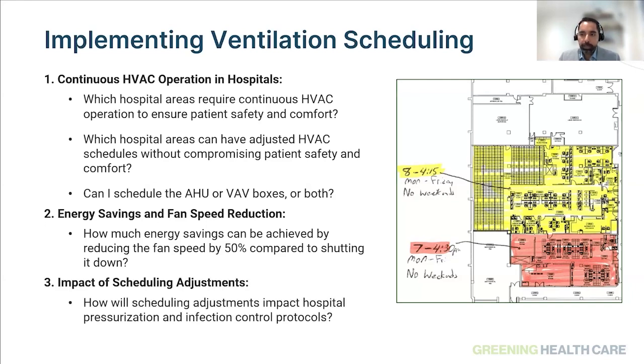I touched on that. How do pressurization and infection control protocols impact scheduling? If it's done correctly, none of these will impact. In fact, it will make it better, because when you invest in scheduling, you're investing in the ventilation system, which will help you make sure that these systems are calibrated and code compliant, and they take into account the infection control protocols, because you're going to be doing pre and post testing when these schedules are being completed.